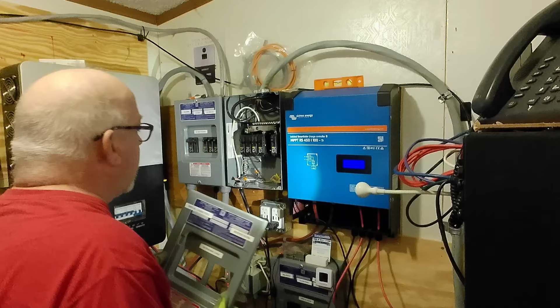If I turn the inverter back on, over here, flip it forward to on, and it switches back over to power through the inverter. So just like it was designed, that automatic transfer switch is working. Alright, now this panel is live again, so need to be a little bit careful and get the covers back on, make sure nothing's going to be shorting out.